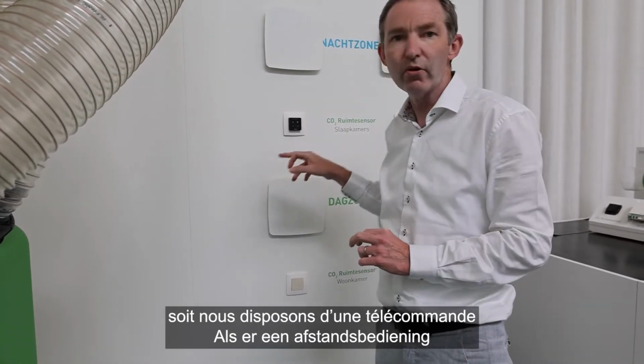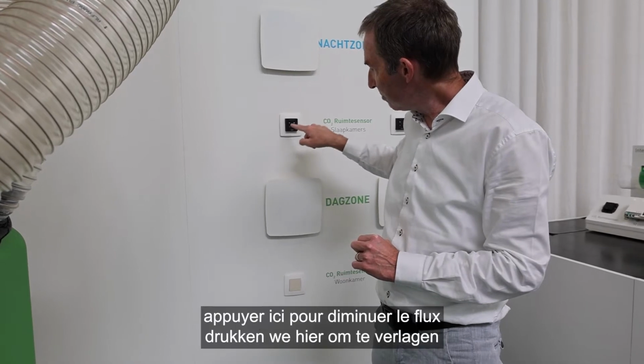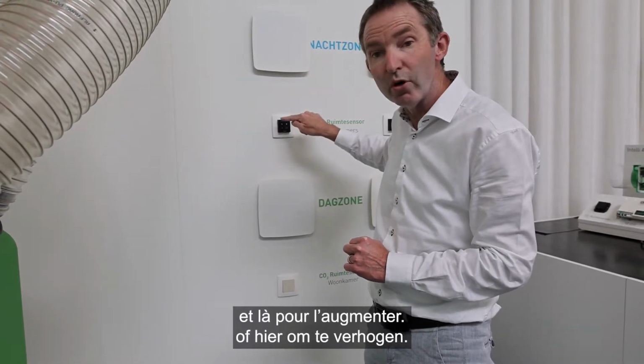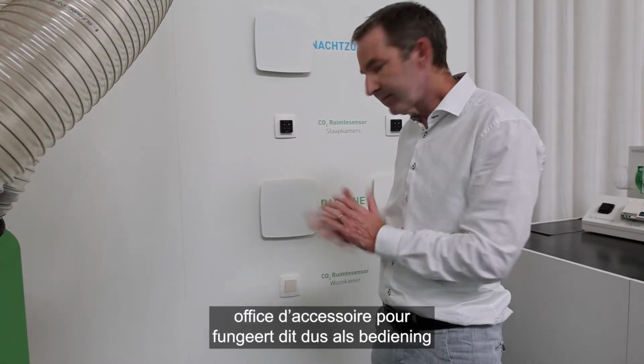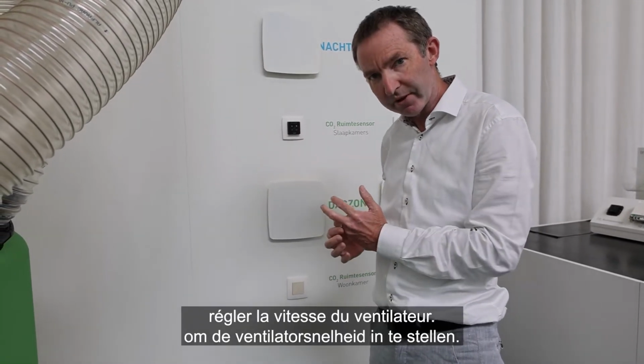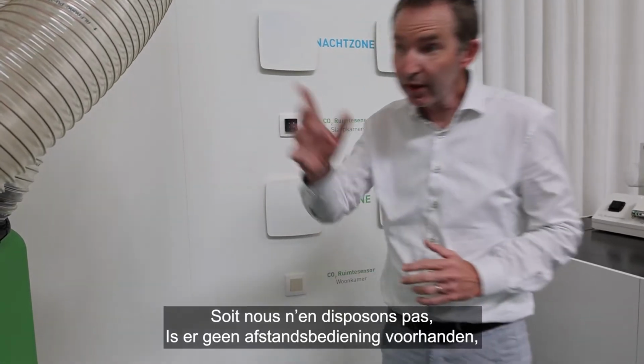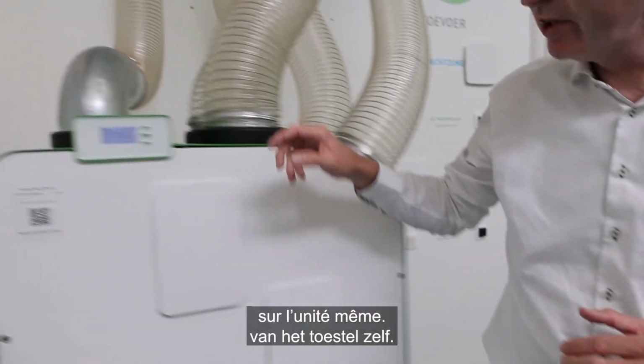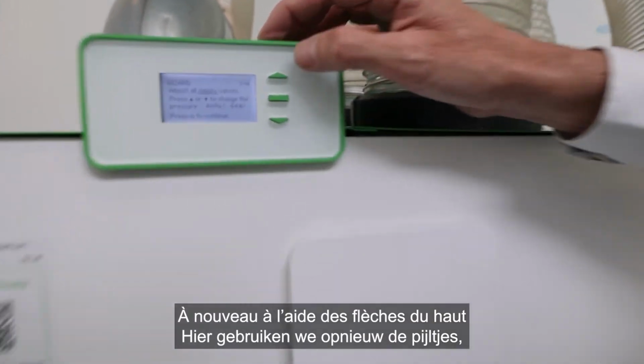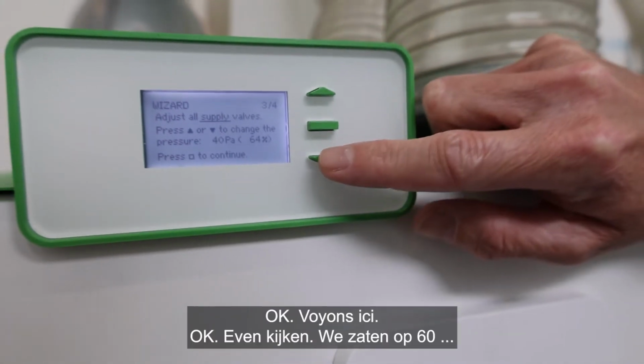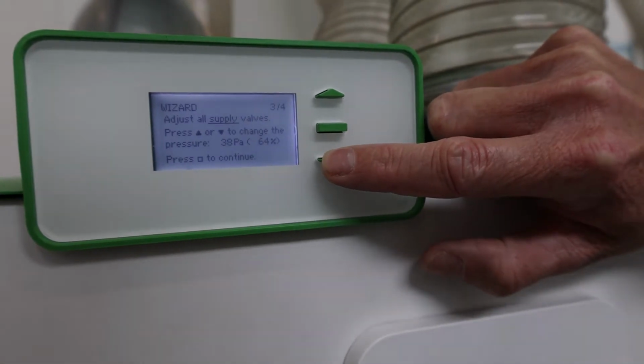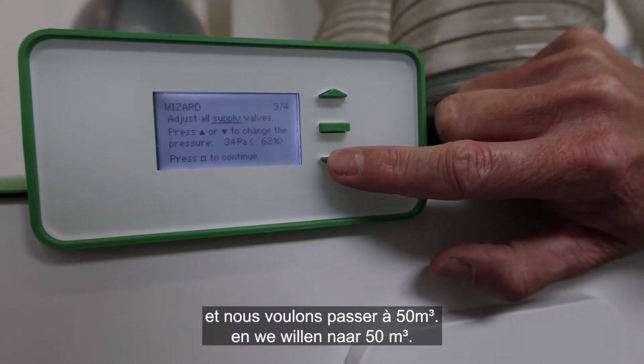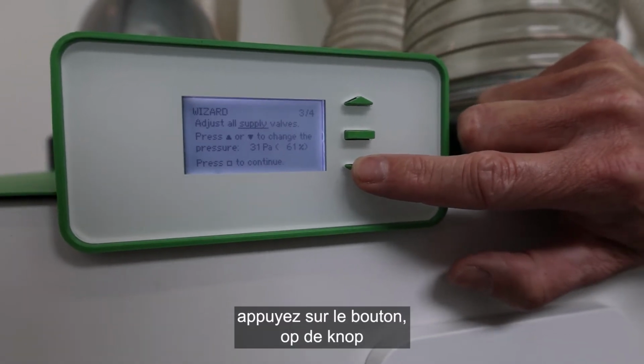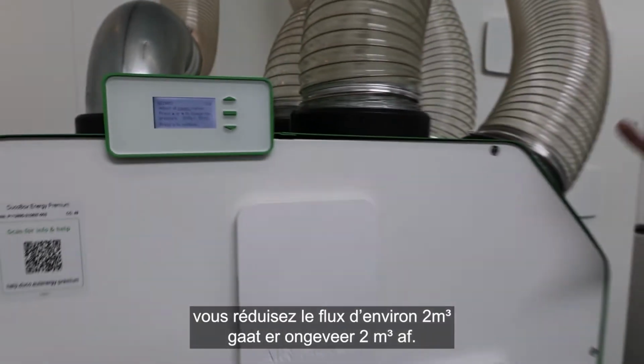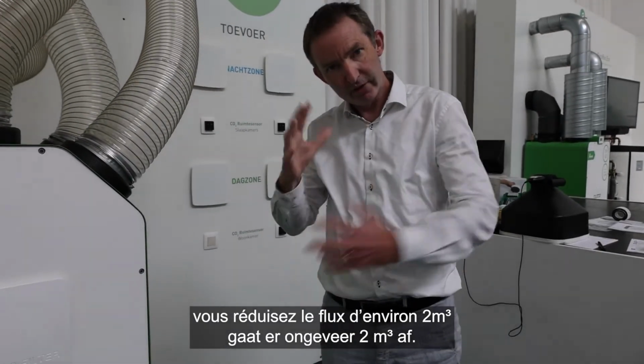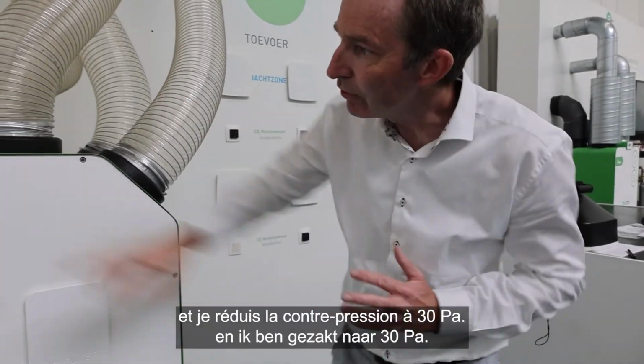Either if there's a remote control in the neighborhood, we can push here to go down or push there to go up. So basically that serves as an instrument to settle the fan speed. Or if there's no remote control available, we can actually do it on the display of the unit itself. So here again with the arrow up or the arrow down. Okay, so let's see here, we were at 60 cubes and we want to go to 50 cubes. Approximately each time you press the button, it's approximately 2 cubes that go down. Okay, so I've pushed now and I've lowered it to 30 Pascal.